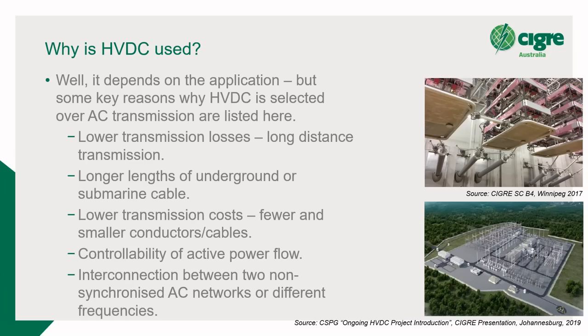The second point there is longer lengths of underground or submarine cable. So typically with AC cables, there are limitations to how long you can run your AC cable before you need to start installing a significant amount of reactive plant or compensation along the way. And of course that gets worse as you get up to the higher voltages. So there's generally a rule of thumb, depending on the voltage, sort of 50 kilometers, 100 kilometers, where it's just not practical to run that point-to-point transmission in AC using cables. So this is where HVDC often comes to the fore, and particularly where you have a long stretch of water. If you can imagine Basslink, where the stretch of water there is about 300 kilometers, it gets to the point where DC can be the only option.